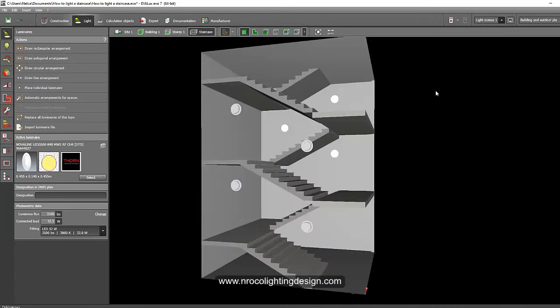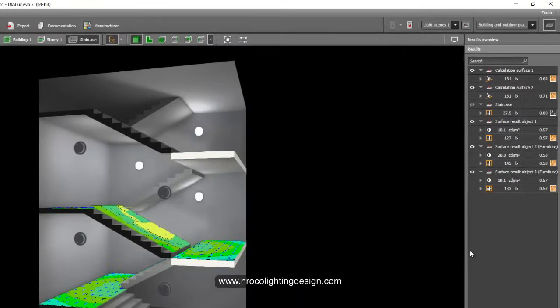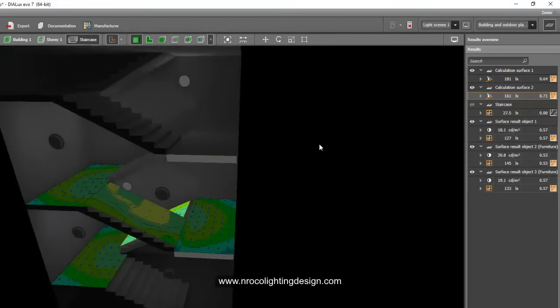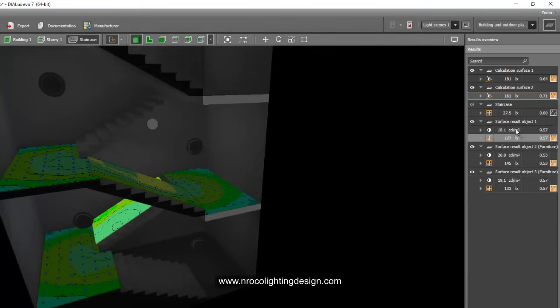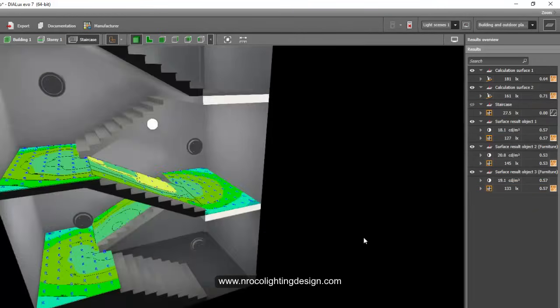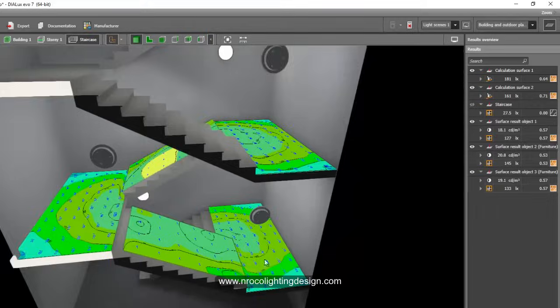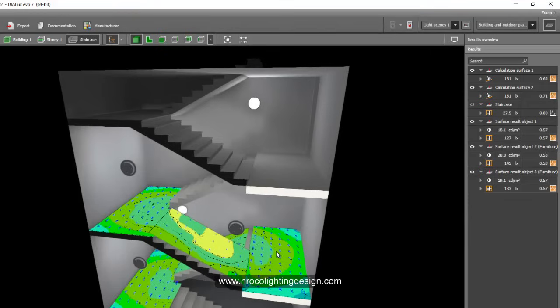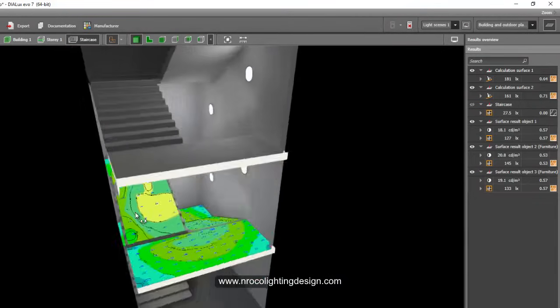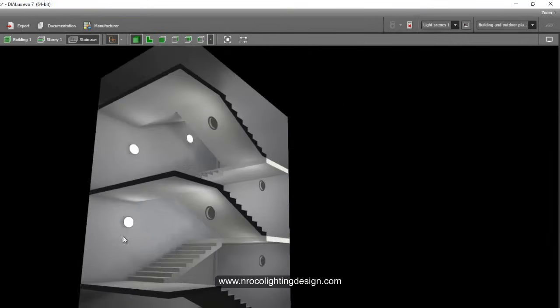Discard the previous result and run the new calculation. The results show 181 lux on one surface — great! 161 lux on the other side. On the treads and risers: 145, 127, and 133 lux. The landing is less bright now, but the tread and riser — the most dangerous part of the staircase — are brighter, which is acceptable.